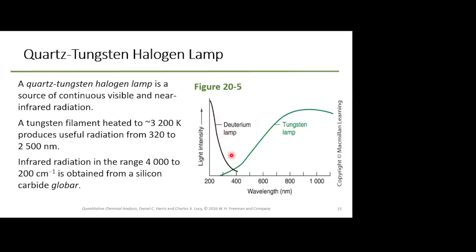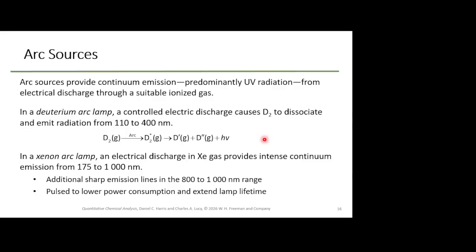And this right here is the deuterium lamp. You can use this for the lower wavelengths right here. That would be below 400 nanometers. Notice that there isn't really a single light source, though, that you can use and covers every region, right? Okay. By the way, this is the reason for the huge difference in price between a UV vis instrument and just a visible light instrument, if you're ever wondering. Because visible light instruments can just use LEDs to cover the different parts of the spectrum, whereas a UV vis instrument needs more advanced lamps. More pricey lamps, I should say.